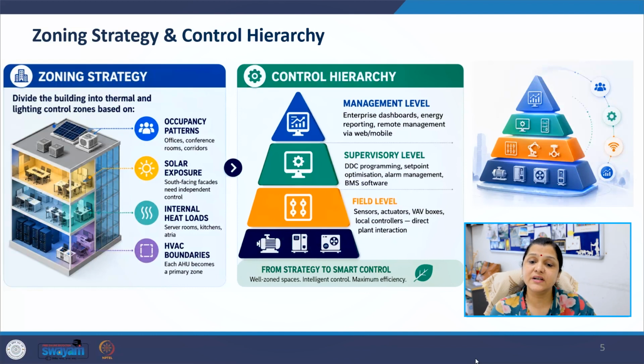After zoning, we define the control hierarchy. At the management level, we have dashboards, energy reports, and remote monitoring systems. At the supervisory level, we have DDC programs, set point optimization, and alarm management. At the field level, we have sensors, actuators, and local controllers directly interacting with equipment. This layered structure improves efficiency, scalability, and fault management.